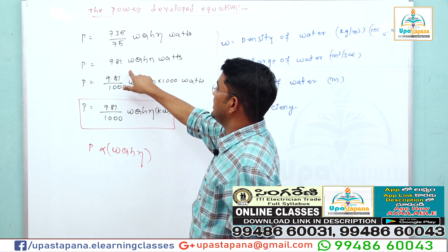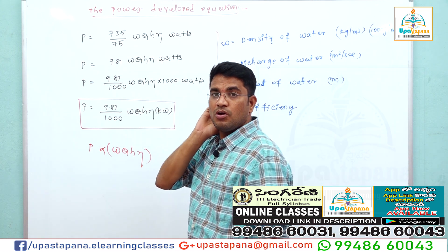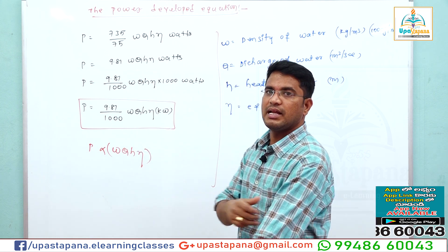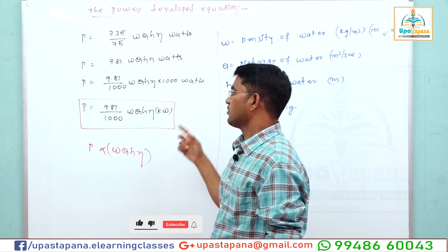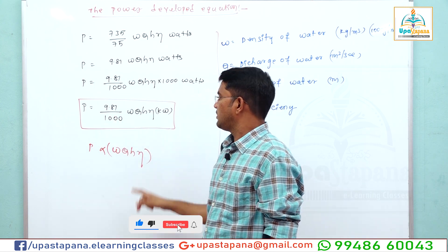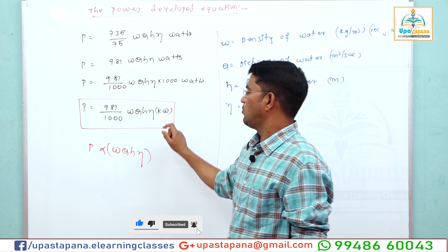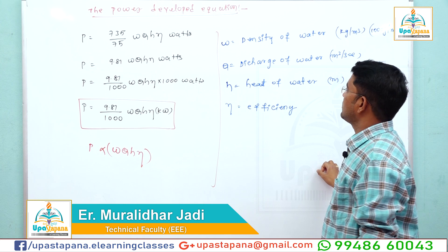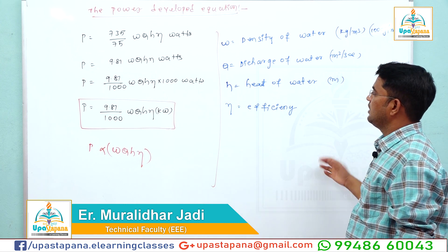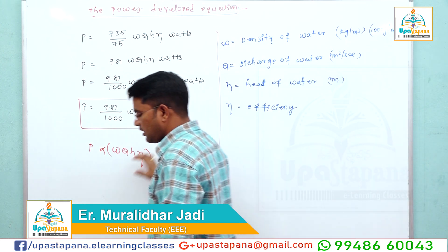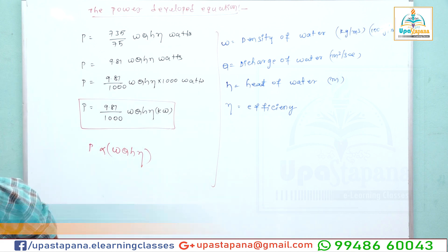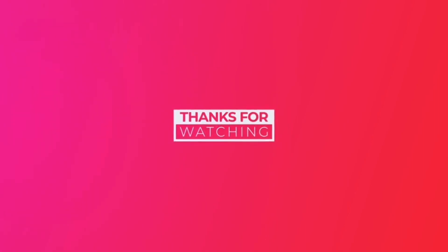The power developed equation in the hydel power plant is: P = 9.81/1000 × W × Q × H × η kilowatts. Where W is the density of water, Q is the discharge of water, H is the head of the water, and η is the efficiency. This is the power developed equation.